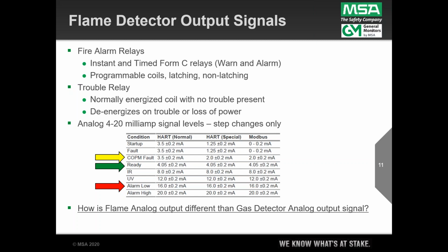What that means is there's a programmable time delay function using a rocker switch in the device, and if you say 8 seconds, for example, then the fire has to be above the threshold setting for a continuous 8 seconds, and at that point the sustained or timed relay would energize. Both are programmable in terms of normally energized or de-energized operation with no alarm state present, and then latching or non-latching contacts. The third relay is a trouble relay, and this is always normally energized with no trouble present, and that relay will de-energize on a trouble state, normally dirty windows, could be low power, or a loss of total power. So it de-energizes when the device loses power. So it's a dual role relay, trouble and loss of power.